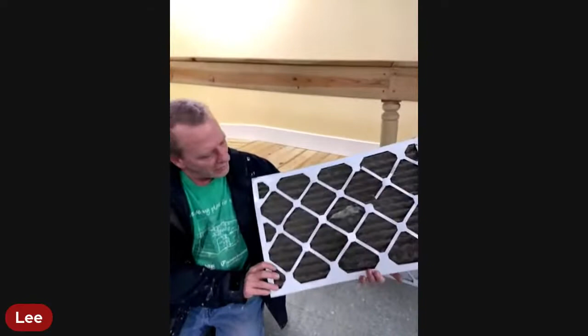Here I can see there's evidence of pieces and stuff, and I'm like, this is not good. What this is doing is starving that motor. The motor keeps working to pull air through that filter, and it will burn itself out. That's one of the leading causes of self-destruction of furnaces, that they just don't change their filters.